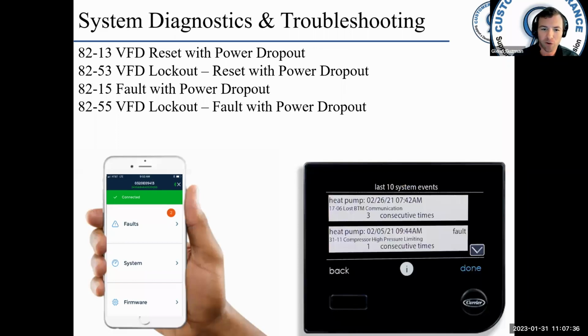8213 VFD reset with the power drop out. 8253 is the corresponding lockout. 8215 fault with the power drop out, and then 8255 lockout. Okay. These are power related, power drop out faults. Typically, I see these in the middle of the summer. And in Florida, we have our mid to late afternoon storms. The storm rolls through, and then an hour later, 2 hours later, hey, the unit's still off, and you get 8253, 8255, whatever. Okay.